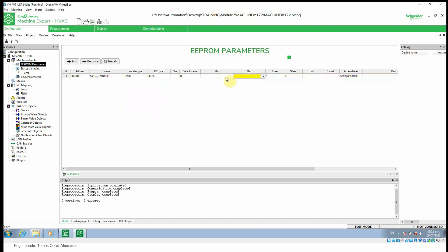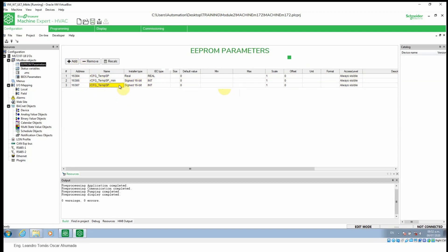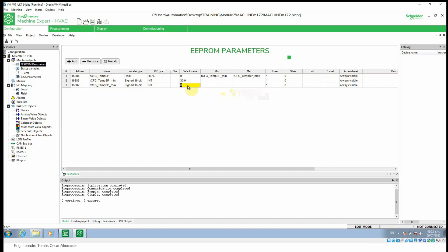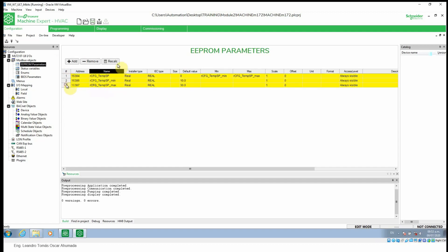We can use the minimum and maximum value, and we can link this to another variable. For example, if I want to use min and max, I can select min and max and set a default value. Something important here is the address of the variables — we can make mistakes here. This is a real variable and it takes two words. So in order to make this work, we can use the Recalc operation and the address will be corrected automatically.